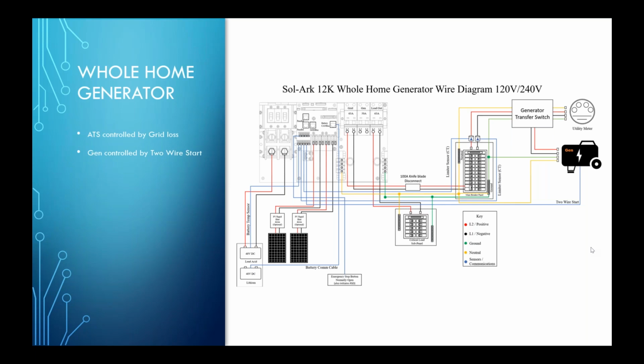Obviously, everything else is pretty standard as well, with the critical loads panel that would be powered up. So in this case, what would happen when the grid fails is that the generator would turn on either by the transfer switch itself or by the 2-wire start if available. So if you want to allow the batteries to be used in an off-grid situation, we can have the 2-wire start be turned on once they're depleted to a specific level that you program. Once the generator turns on, that will allow the customer to take full advantage of the whole home at that point, and then we will use that power to support the critical loads and even help charge the batteries.